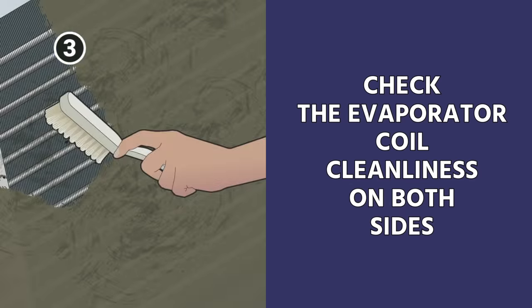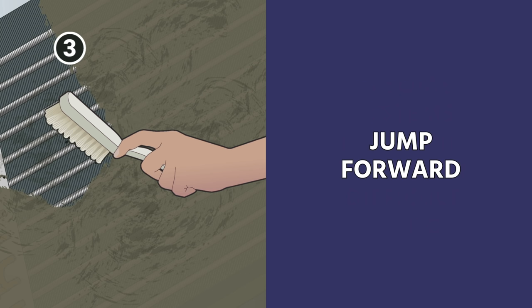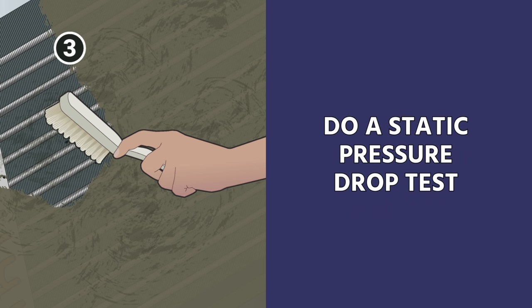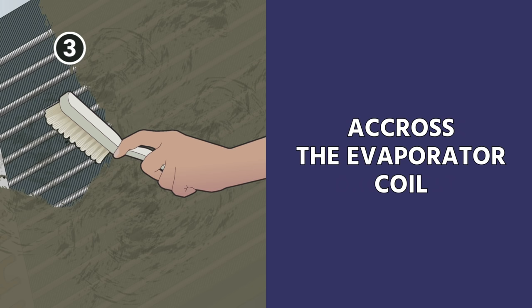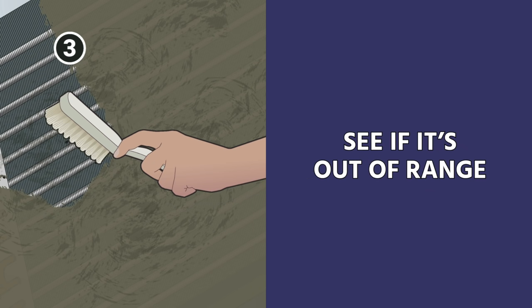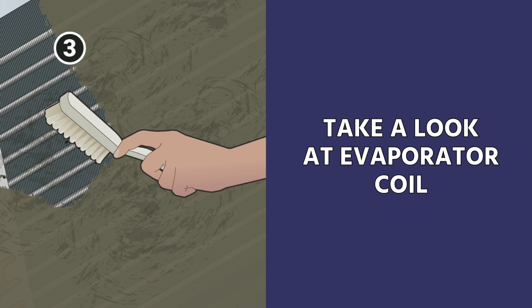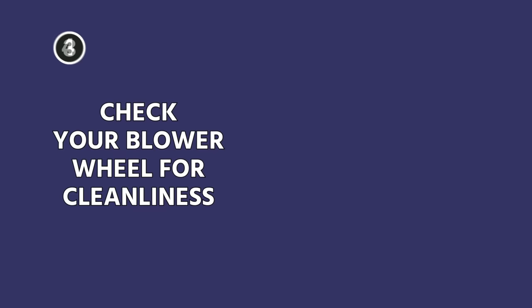Next, check the evaporator coil cleanliness on both sides. In some systems this can be very difficult to do. If it is very difficult, you can jump forward and do a static pressure drop test across the evaporator coil — that's easier — and look at the manufacturer specifications to see if it's out of range. For most of us, though, it's going to be just as easy to take a look at that evaporator coil and see if it is visibly dirty.